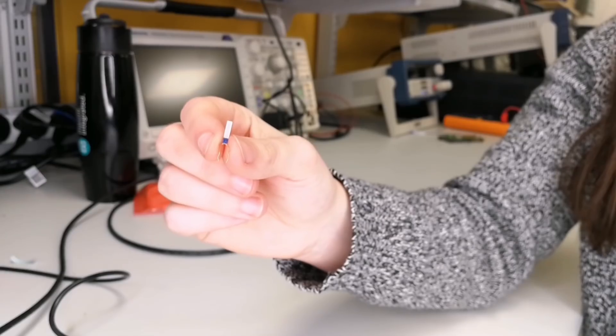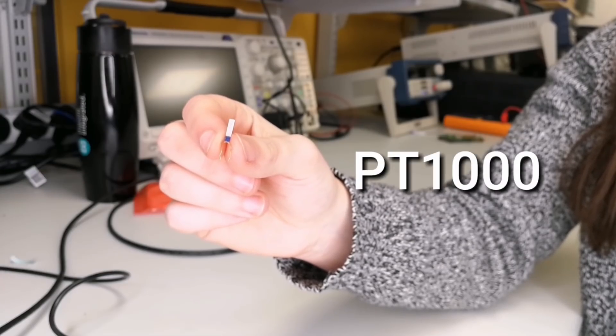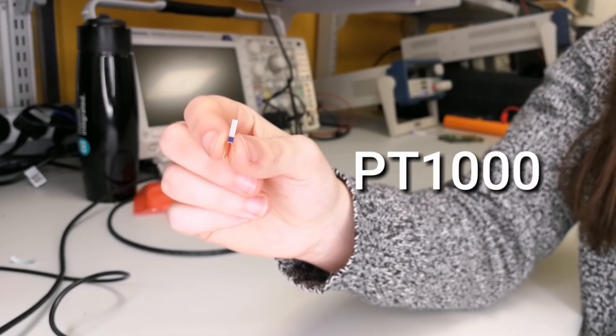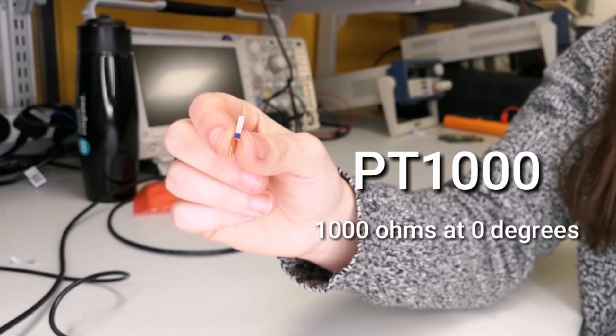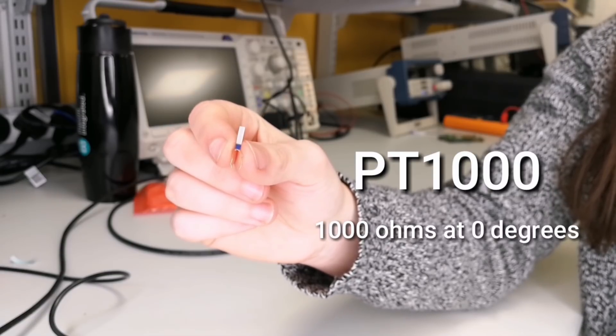RTDs are specified based upon their resistance at zero degrees. So for example, this is a PT1000. That means it's an RTD made out of platinum whose resistance is 1000 ohms at zero degrees Celsius.